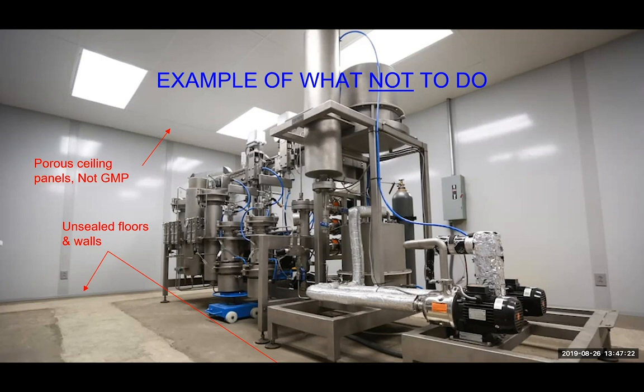Here's a quick example, which we're picking on a little bit, of a place that's unfortunately going to have issues becoming GMP compliant. The reason is simple stuff: they can't bring the building back to reset. We're not picking on that piece of equipment in the foreground, we're actually picking on the facility around it. Those floors are unsealed, therefore porous, allowing lots of pathogens in them. They can't be cleaned properly and can't be reset back to zero. The same thing with the ceiling, that's acoustic tile, completely porous, can't be reset. We've also got panels that are not washdown rated, and a bunch of plugs that look like they're not washdown rated either. These are simple things a lot of people don't think about: if you need to take a room and bring it back to a complete cleanliness standard, which GMP requires, you have to have that ability within the design. Otherwise, you're just not going to get it.